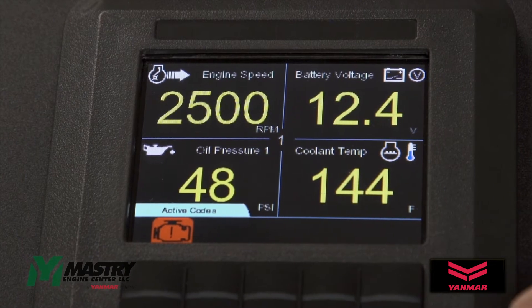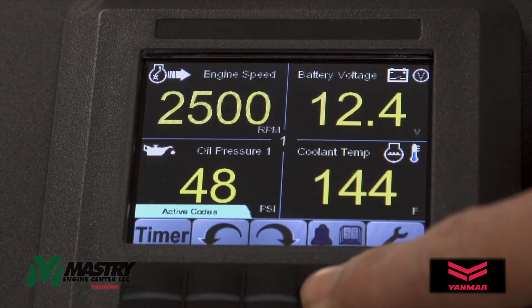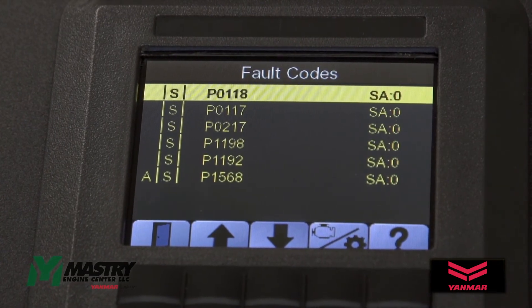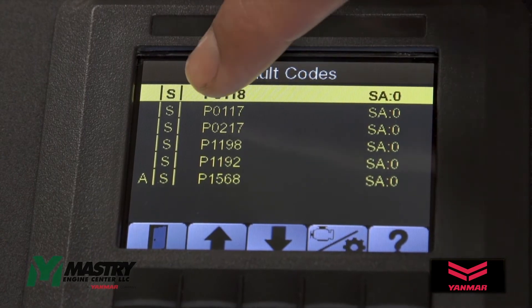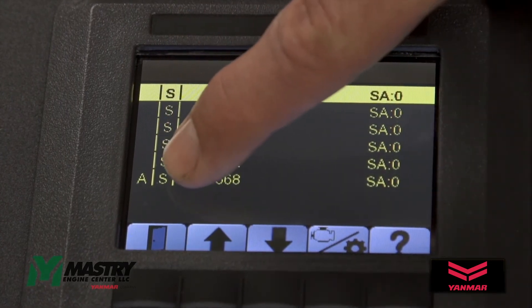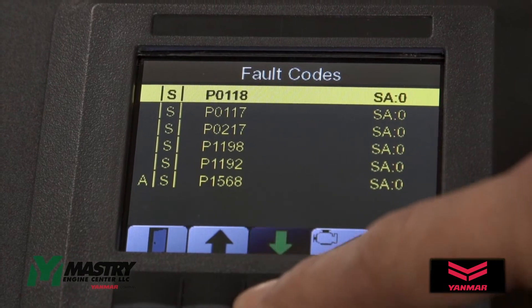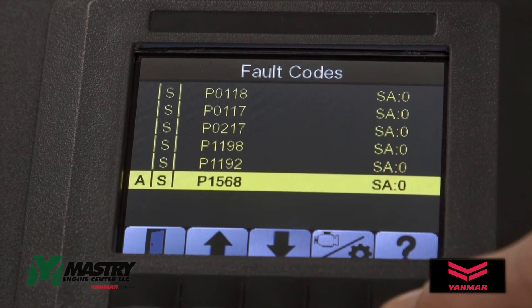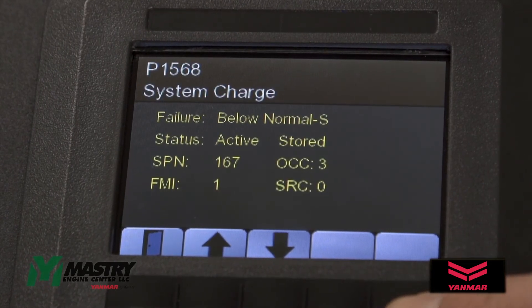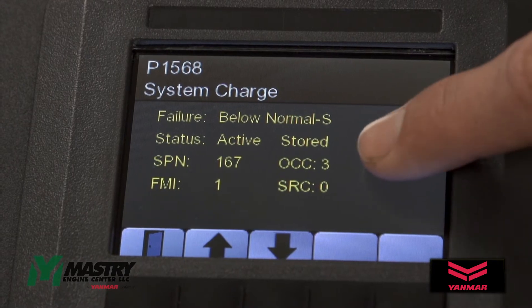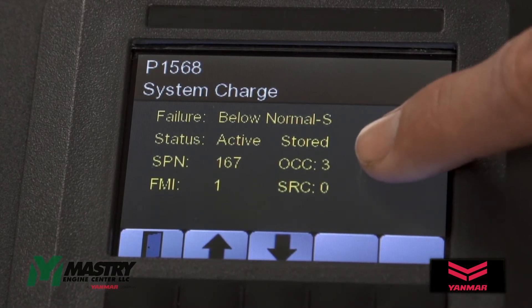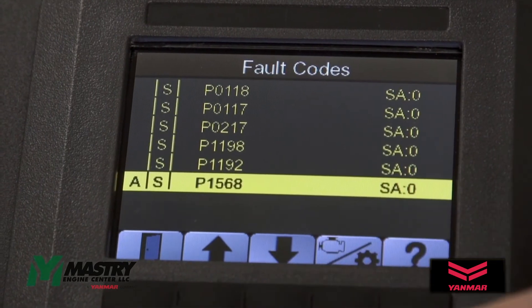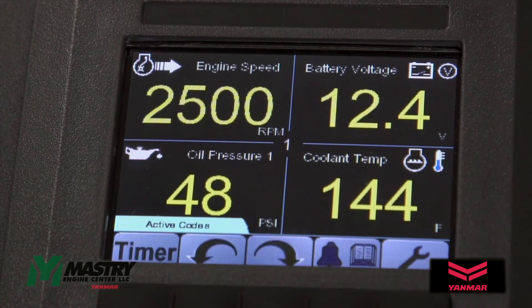To get more information about the trouble code, press any soft key and then click on the bell icon, and then you can see a list of all the stored and active fault codes. The stored codes are indicated with the S, and the active codes are indicated with the A. To get more information about a particular code, scroll to the code and then click on the question mark, and you can find more information about the code, as well as the number of times that this particular fault code has occurred. To exit out of this menu, press the exit icon and then continue until you get to the main menu.